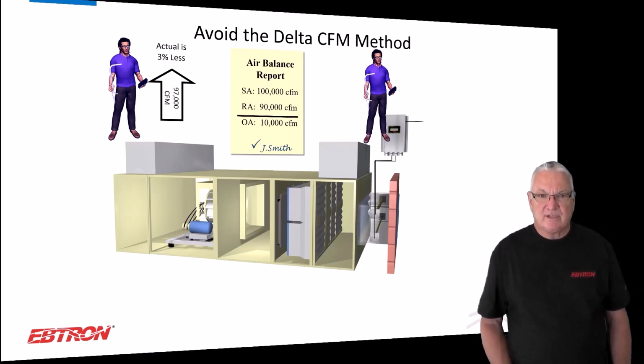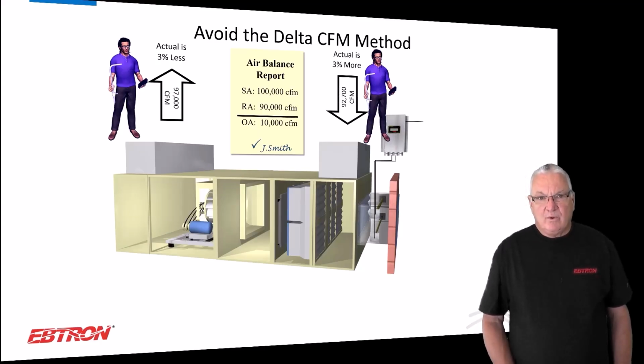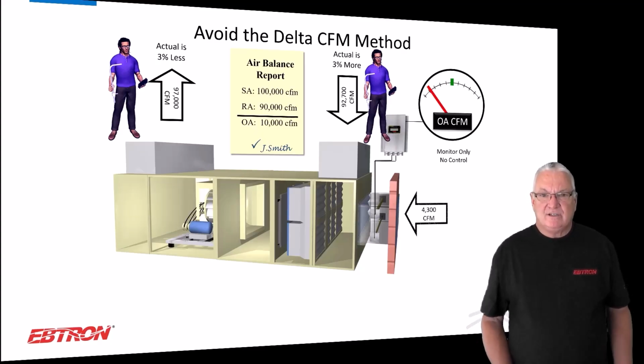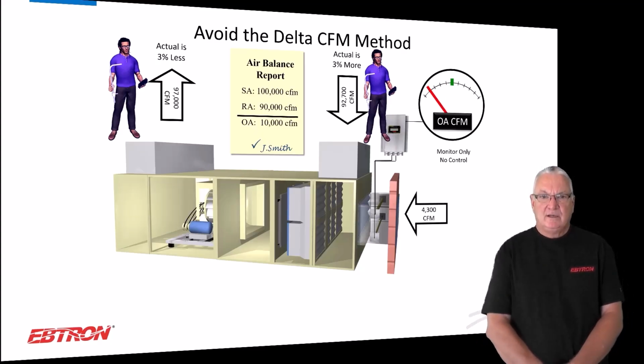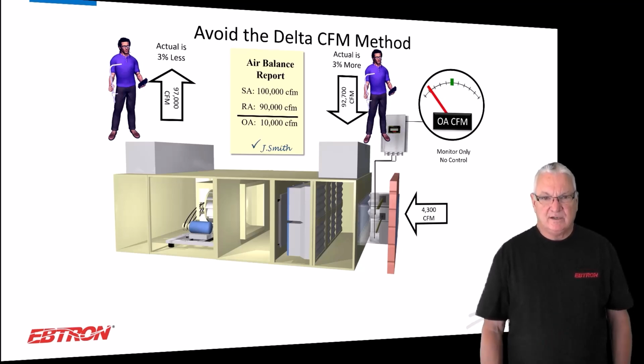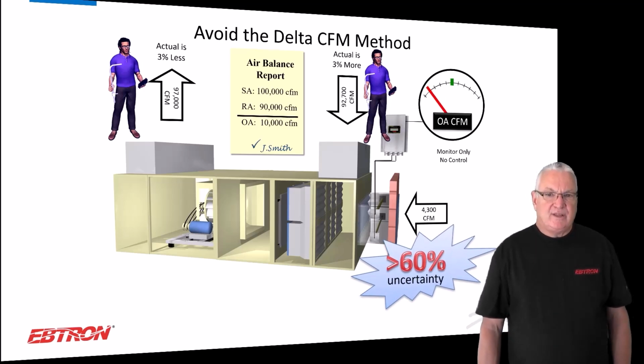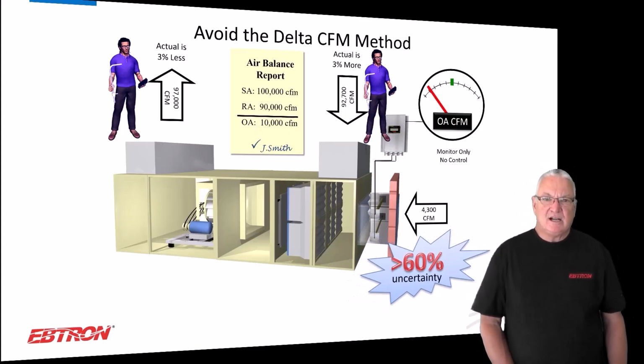So when we measured 100,000 CFM, it could be 3% less, so that's 97,000. And when we look at the return side and we measure 90,000, it could have been 3% more, which is 92,700. So the difference of 10,000 was really 4,300. I'm not doing rocket science math here. You just have to look at it and ask what the uncertainties of the measurement are. And that's not acceptable. It's not going to work.